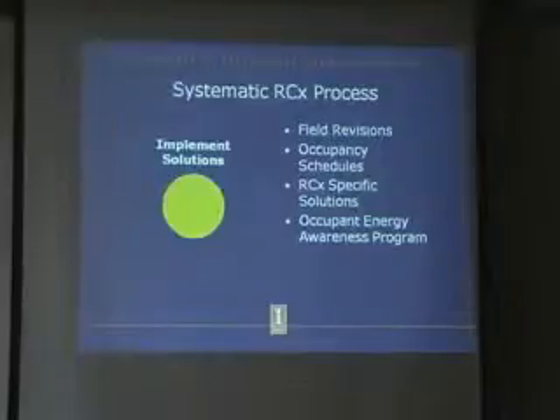Next process is to implement the solutions. These are all going on simultaneously. The gentlemen out in the field are out there tweaking and calibrating the temperature sensors, humidity sensors, making sure the system runs through its steps properly. We're inside talking and having meetings, as Carl mentioned, with the facility manager, looking over the occupancy schedules, seeing if we can agree on certain times to cut back the systems, and different other specific solutions that we have in our cheat sheet.